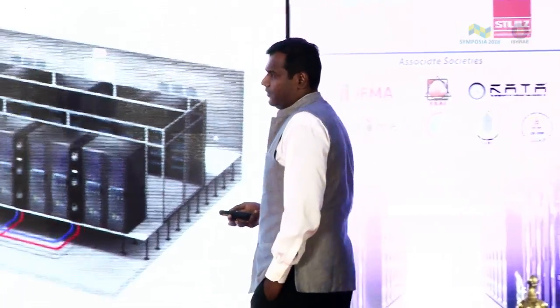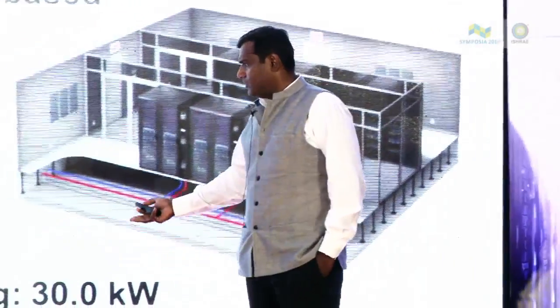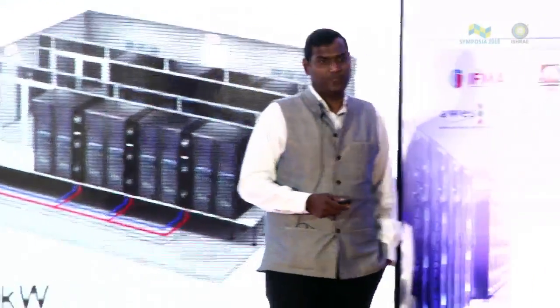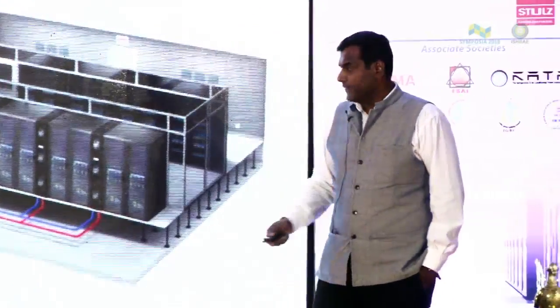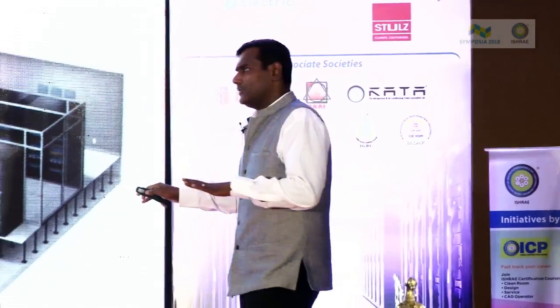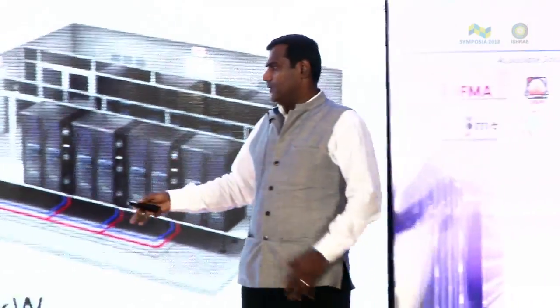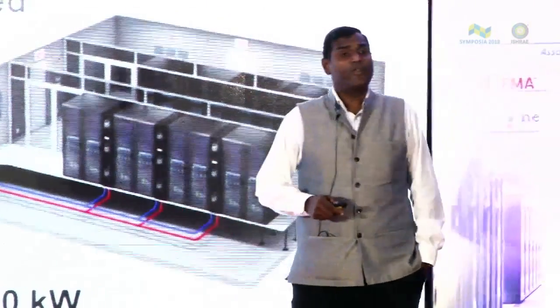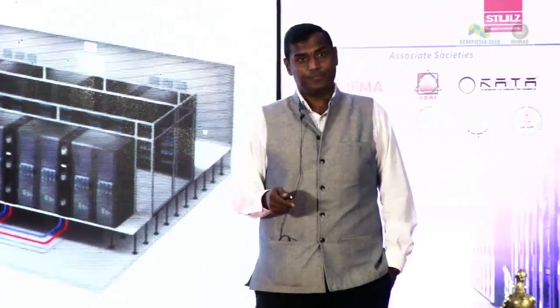In such a scenario, we're still talking about consuming 30 kilowatt of power for cooling and a partial PUE. This is not the PUE of the data center. It's a partial PUE because this takes into account only the cooling part of energy consumption, not the total energy consumption for other components. And we are talking of 1.47, which is already very good.